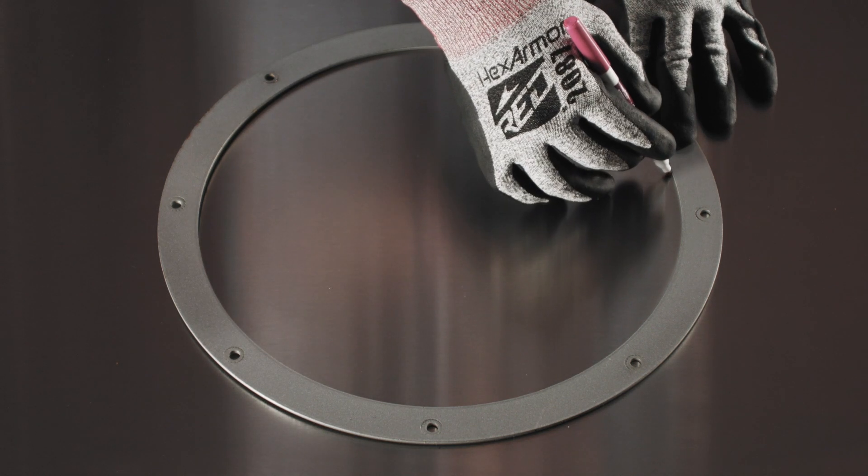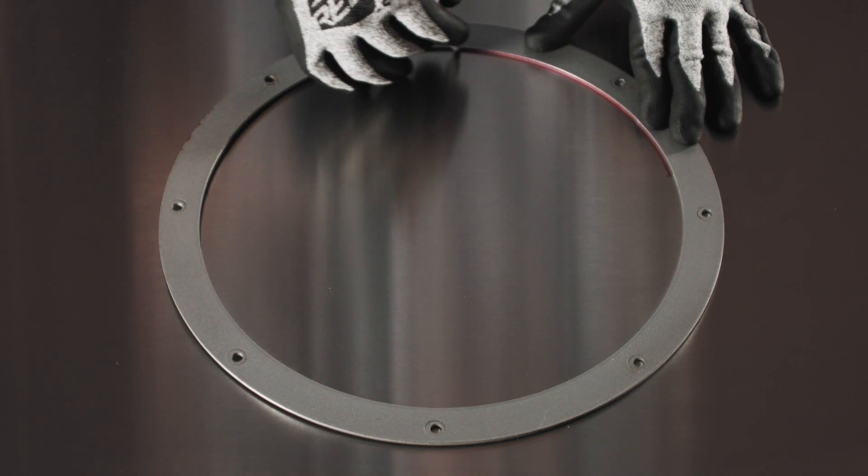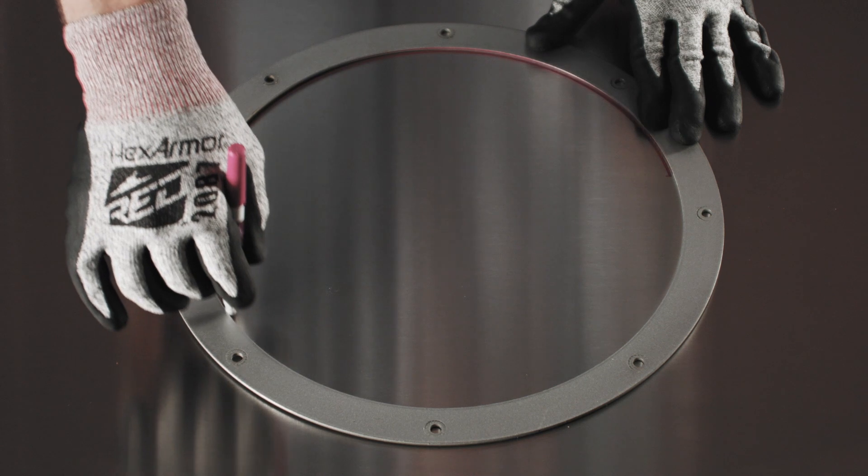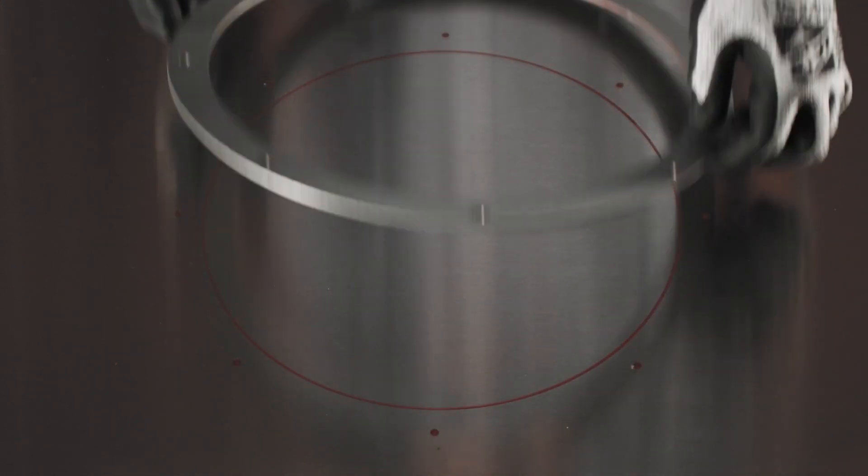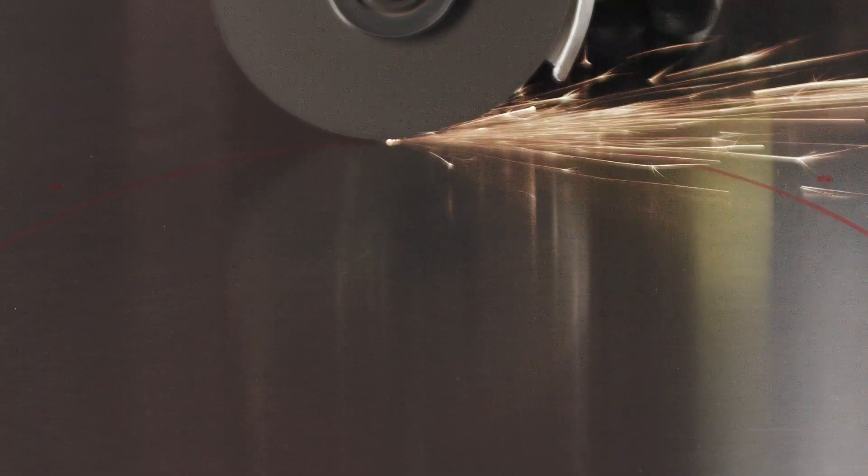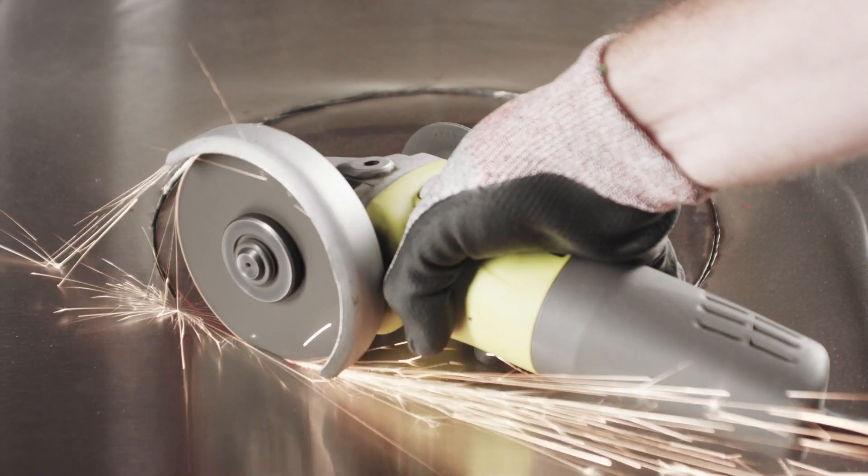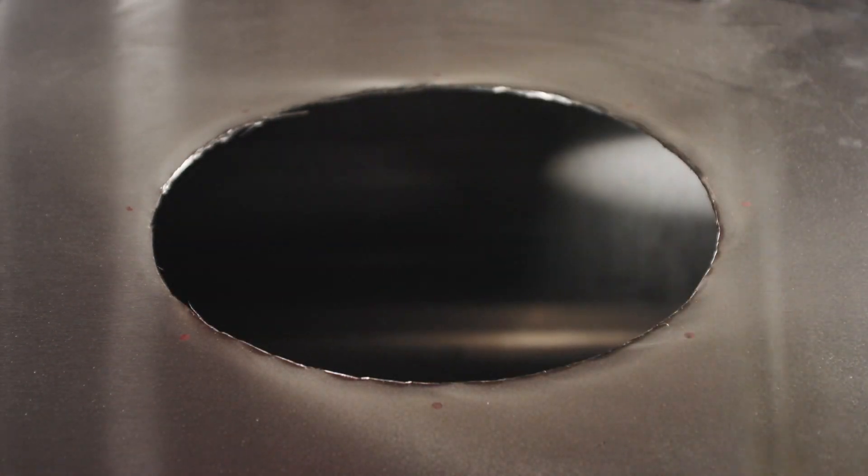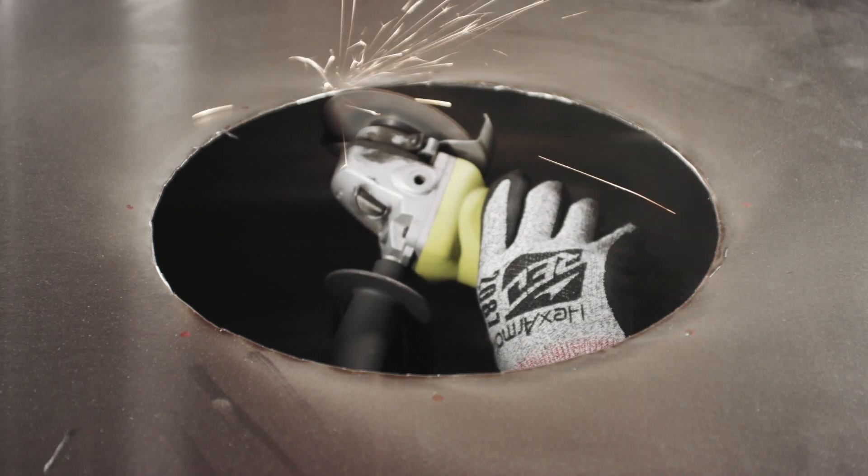Since the riser will be bolted on, a bolt hole circle is required. Use the loose ring as a guide to mark the inner diameter, as well as the bolt hole locations. You can now cut the plenum along the inner diameter you just marked using an angle grinder. Make sure to deburr and smooth the hole.